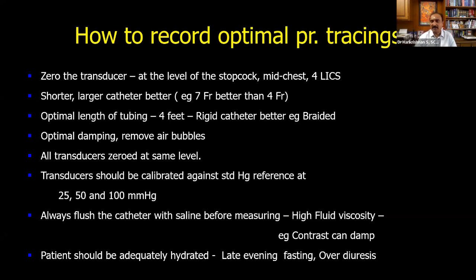Optimal damping. You have to remove air bubbles, otherwise, as you must have experienced, whenever there is an air bubble, the pressure dampens. And if you have multiple transducers, for example, if you are doing a balloon mitral valvotomy, you have to have 2 pressures. Both transducers should be zeroed at the same level and also should be calibrated against a standard reference. Ideally it should be at 0, 25, 50 and 100 millimeters. Ideally you should do that, especially when you are doing a very good hemodynamic study. And always flush the catheter with saline before measuring. A fluid with high viscosity, for example contrast, can damp. So that is always very, very important. And also, for example, if you take a patient in the afternoon at 4 o'clock, the patient is fasting from the morning, most likely the RA mean will be very low.